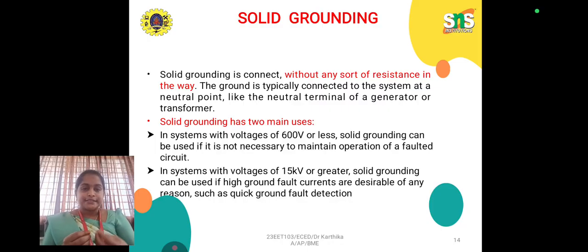In systems with 15 kilovolt or greater, solid grounding can be used if high ground fault currents are desirable for reasons such as quick fault current detection. It is used in both ways: for 600 volt or less, and also for systems with 15 kilovolt or greater.